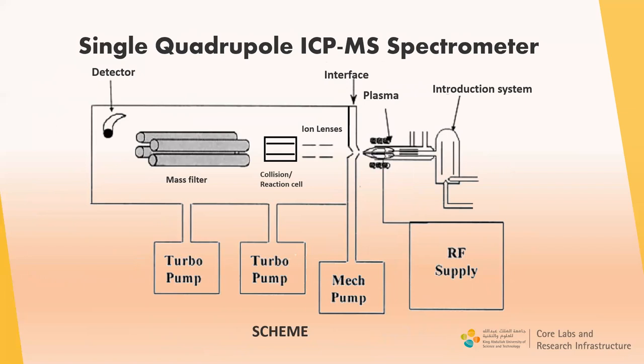As 90% of all ICP-MS spectrometers used in laboratories worldwide are quadrupole mass spectrometers, today we will consider the principles and applications of this type. The key parts of the quadrupole ICP-MS spectrometer are: introduction system, plasma, interface, ion lenses, collision reaction cell, mass filter, and detector. Let us consider each part in detail to understand the main principles of the quadrupole ICP-MS method.